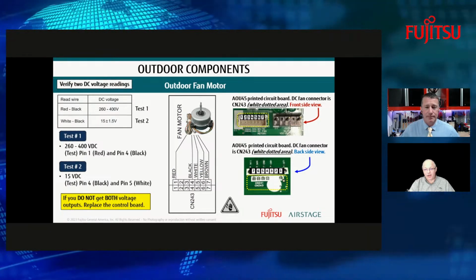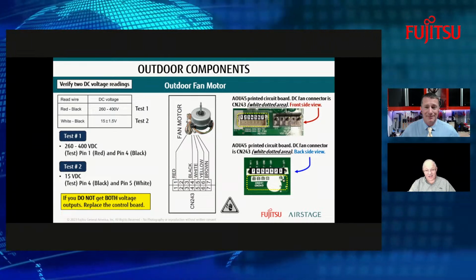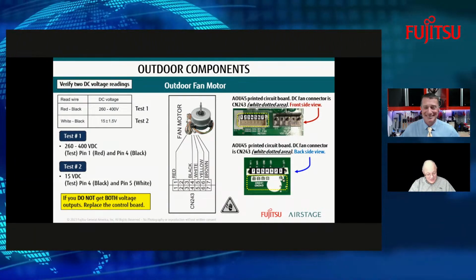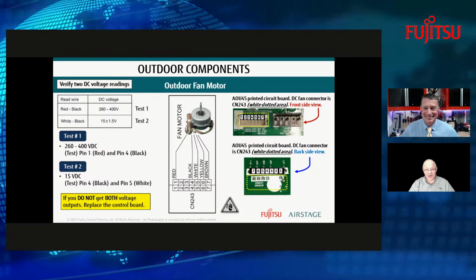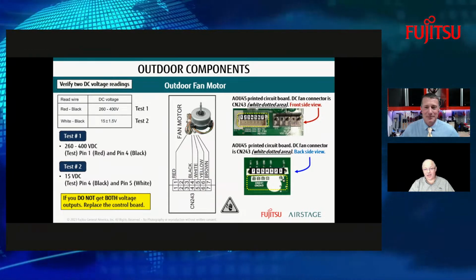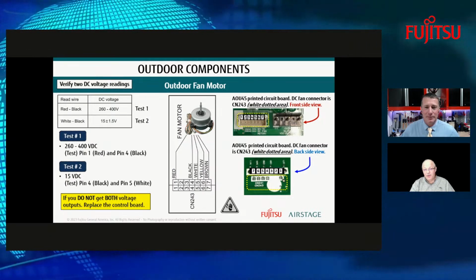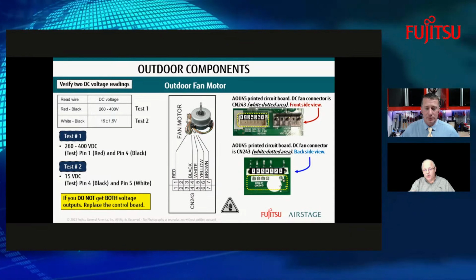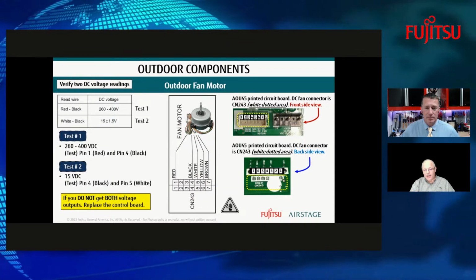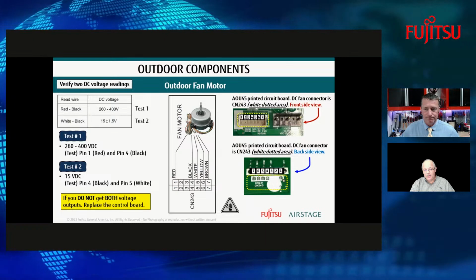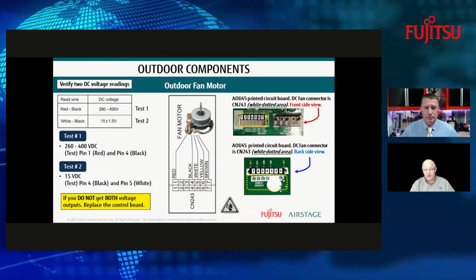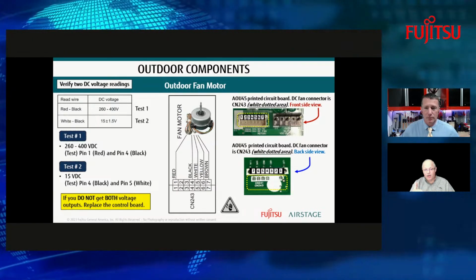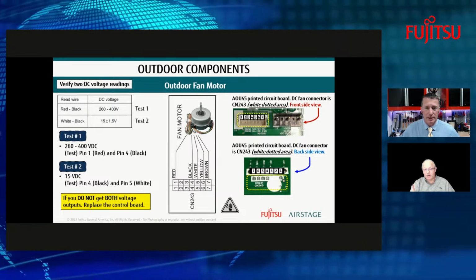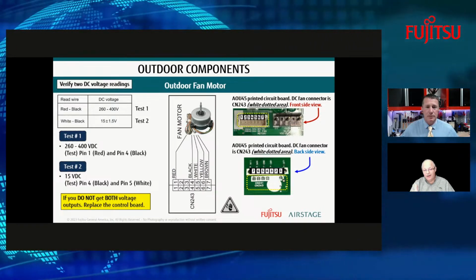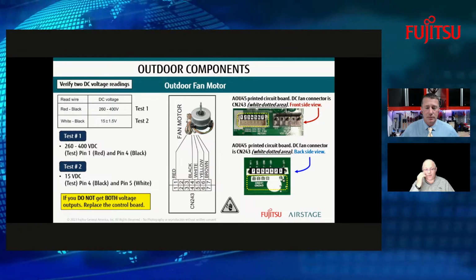Again, you're going to need some sharp test leads. Yeah, I've got to have those micro leads. And you better be very careful whenever you're taking that reading, especially taking it live. So that's the basics of the voltage we're looking at for a motor. And again, it's just a matter of testing the correct pins. You can see that for test one, you're looking at the red and the black wire. Easy enough to check, and then you check the black and the white for test two.